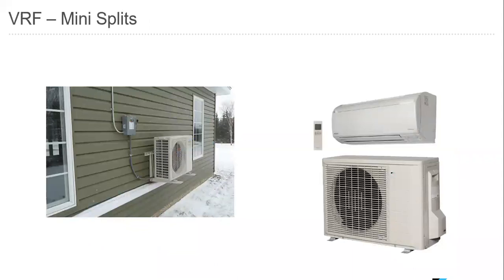Another product that is very prominent in our industry today are mini splits. A mini split consists of an outdoor unit and an indoor unit. Inside the mini split, in the outdoor unit, we actually have an inverter compressor, once again, that is able to speed up or slow down. And we also have an electronic expansion valve. Instead of it being at the indoor unit, it's actually inside the outdoor unit. So that's one of the main key differences between a VRF system and a mini split.